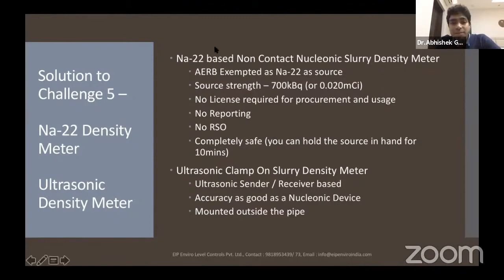Now the question comes up, which device to use? Basically this is an application problem, so we request customers to send us the application details, like the size and diameter of the pipe, the slurry, and the expected slurry density, based on which we take a decision whether ultrasonic would be the best fit or an AERB exempted nucleonic density meter would be the best fit. So again, this is a solution which the industry and power plants were looking for, and here we are with a solution for the measurement.